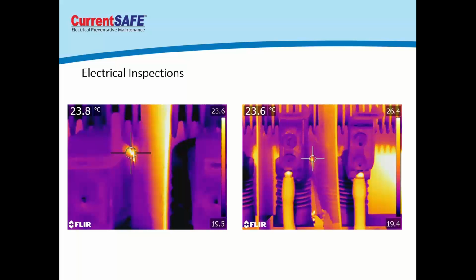Okay, so this has gone to a point where we had to replace and clean the insulator, replace the insulation board, and do some cleaning inside that cabinet and replace some of those insulation components between the phases. So this took an outage on the electrical distribution system in order to make this repair. But we knew if we left it and did not do anything to it, this would eventually build to an arc over potential, and we would have a phase to phase or a phase to ground short. Then that's of course extremely bad. We couldn't have saved a component then.